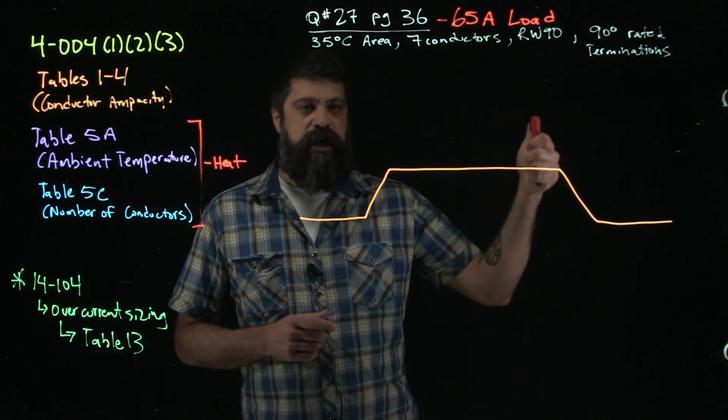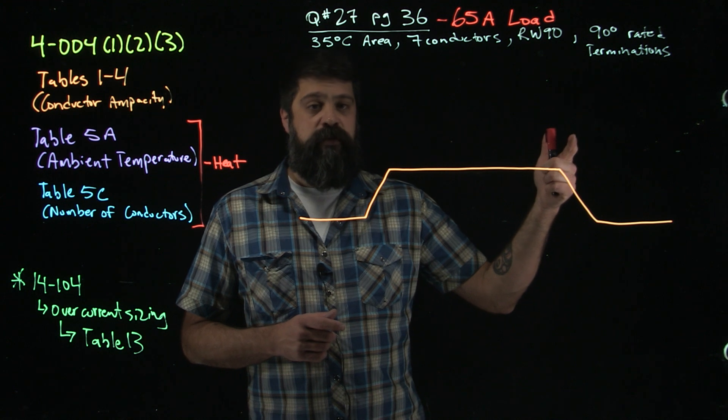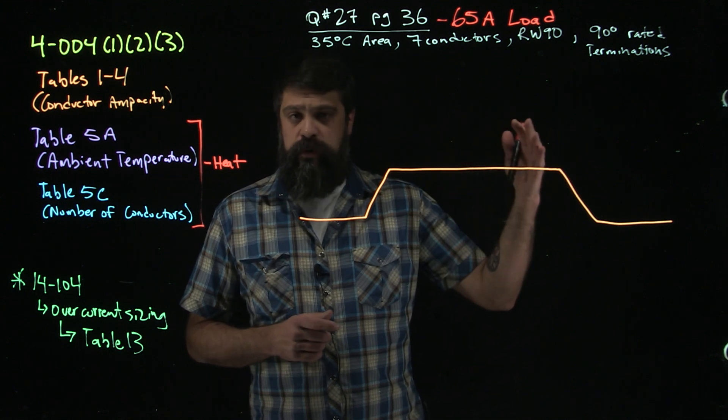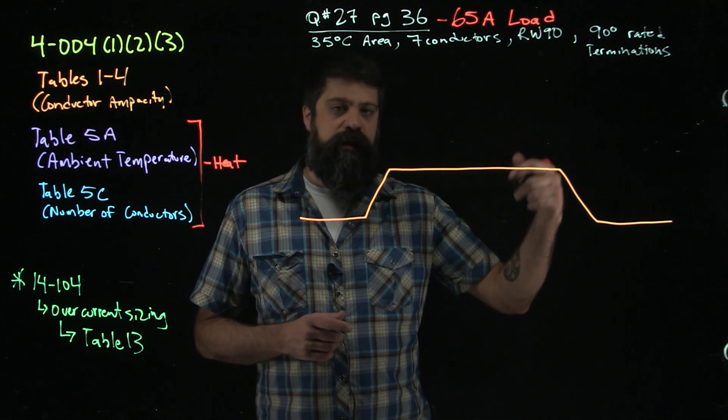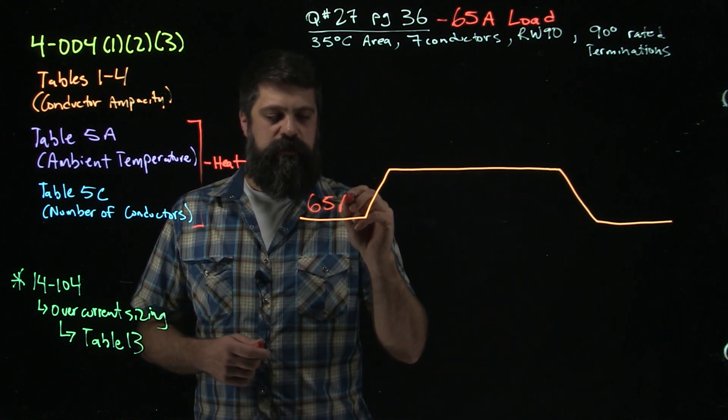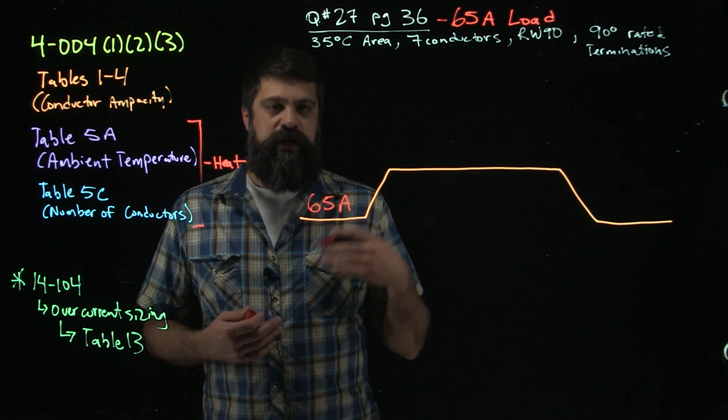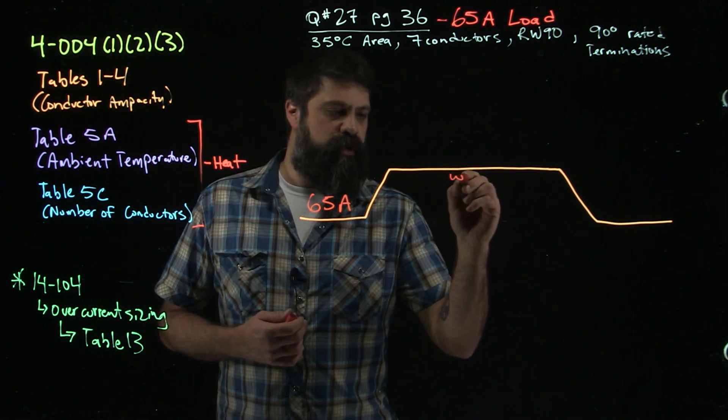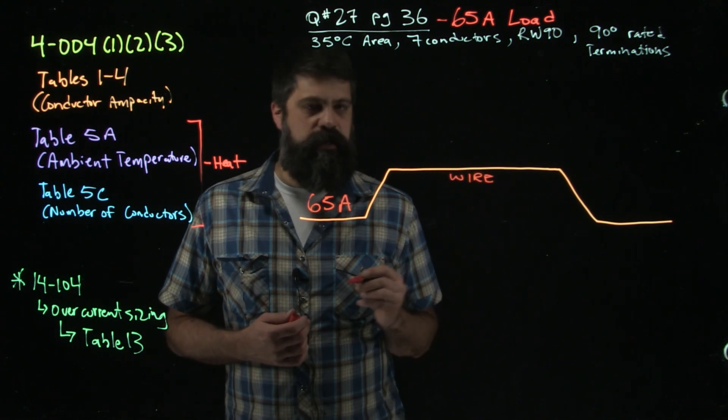90 degree rated terminations means the panel, the equipment, is all rated for 90 degrees. So now when we go into our tables we're going to be looking in that 90 degree column. So we start off over here with a 65 amp load. That's what we're going to be starting with. We need to get it there, so of course we're going to have to run some wire to get over to it.